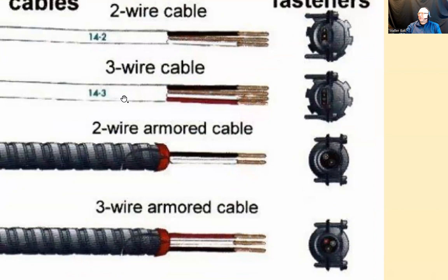All right, now we have 14-3. What do we have? We always have the ground, which we don't count. So we have 1, 2, 3 current carrying conductors. And again, I'm going to repeat, what is a current carrying conductor? A current carrying conductor is a conductor that is supposed to conduct or carry current under normal operating circumstances. You plug something in, a vacuum cleaner, a tea kettle, TV, radio, light, or whatnot. Now, the neutral is always white. Then the first hot is going to be, sorry, the black. Black is always hot. And then the red is always hot. So that's 14-3.